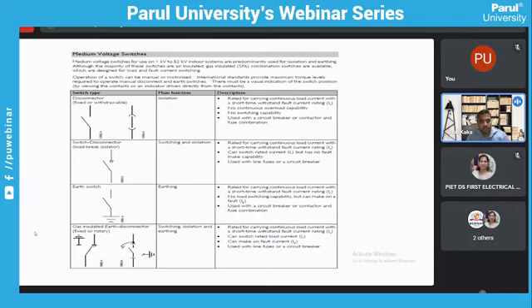Again, this is just a demonstration of the disconnector, switch disconnector, earthing switches, and the gas insulated earth disconnector, fixed or rotary. This earth switch is normally tested to carry continuous load current with a short-time withstand fault current. So the earthing switch also has to be tested according to standards. Normally the earthing switch will be switched only when you have completely isolated your breaker and there is complete isolation from the bus bar. That is how the mechanical interlock in an air insulated switchgear with an integral earth switch has been developed.